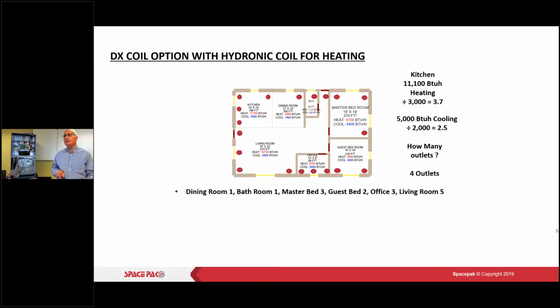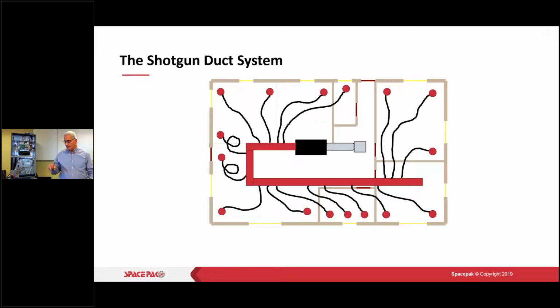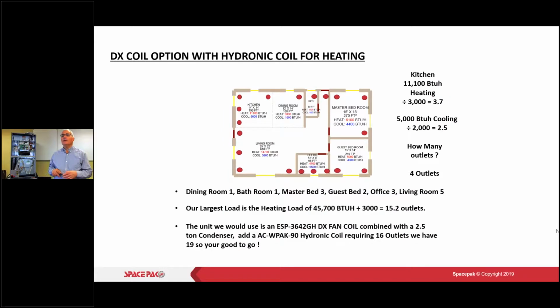If you need help with this, you can contact us. We can help you out, or SpacePak can help you out. So again, the largest load here is our heating load at 45,700 BTUs. So that's 15.2 outlets. Here we'd use a 3642 with the coil for cooling. 16 outlets, so you'll have 19 basically, based on the total output of the system.